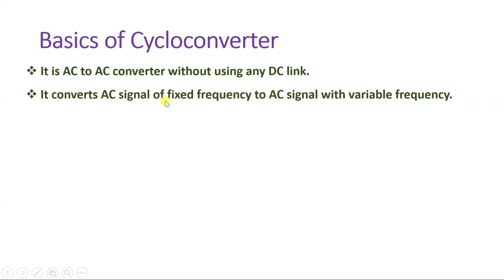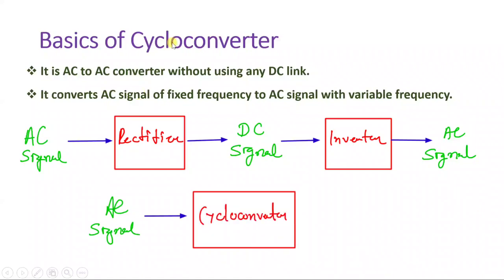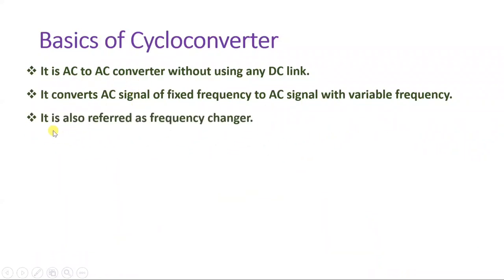A cycloconverter converts an AC signal of fixed frequency to an AC signal with variable frequency. There is another way to change frequency — converting AC into DC and then DC back to AC at a different frequency — but that is very bulky. In a cycloconverter, we directly convert one AC signal to a second AC signal, so it is also referred to as a frequency changer.